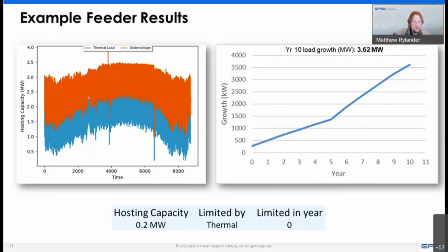When we do this type of hosting capacity assessment, we can see when that worst case occurs - when is the first thing going to break on a feeder? In this example, we might have our first thermal violation at only 0.2 megawatts. If we take into consideration the load growth across the next 10-year horizon, we see that in year zero we're already potentially at a violation point. That's a concern - if we're doing worst case analysis, this feeder won't be able to accommodate much, and we're already beginning to be concerned with this particular feeder.